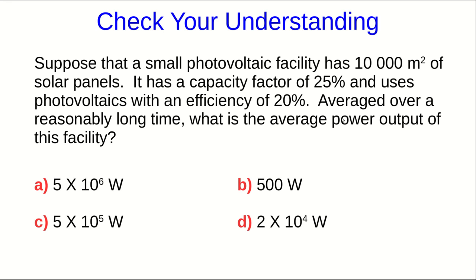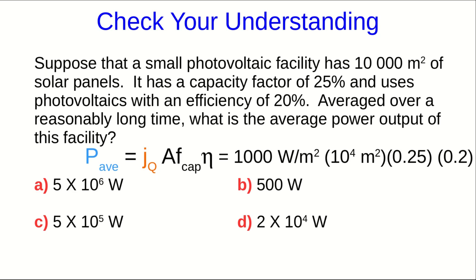The average power is going to be the flux density of the sunlight times the area of the photovoltaics, and then that further has to be multiplied by the capacity factor and the efficiency. So overall, that's 1,000 watts per square meter times 10 to the 4 meters squared times 25 percent and 20 percent, and that comes out to about 0.5 megawatts, which is a very small power generation facility.